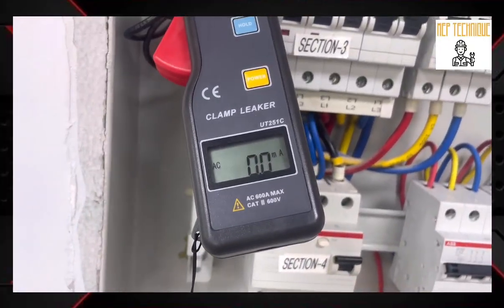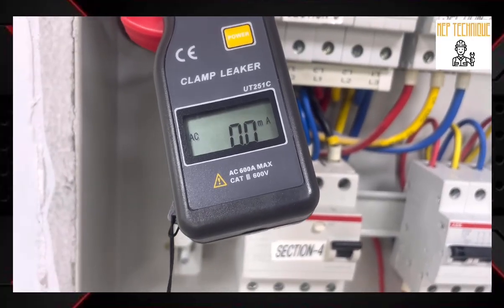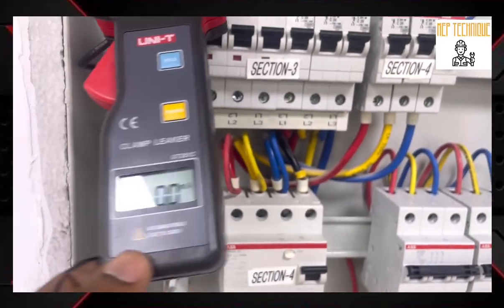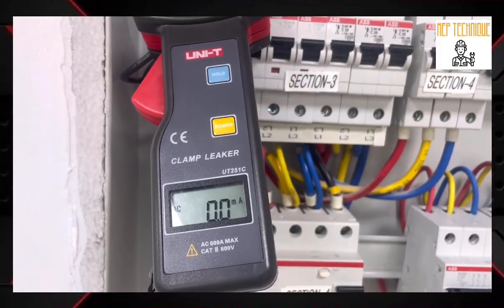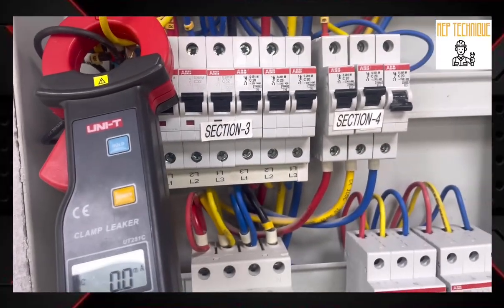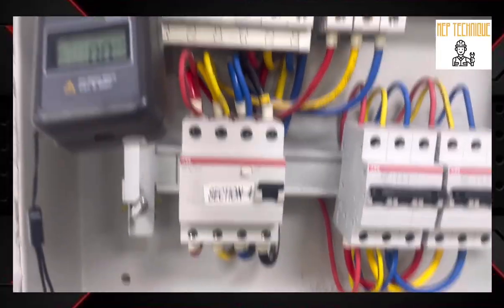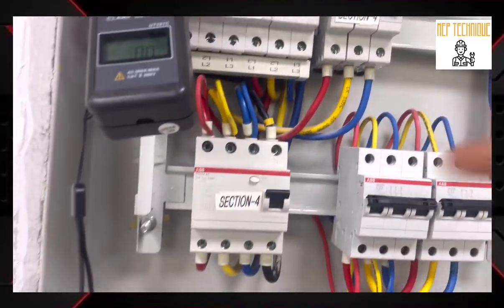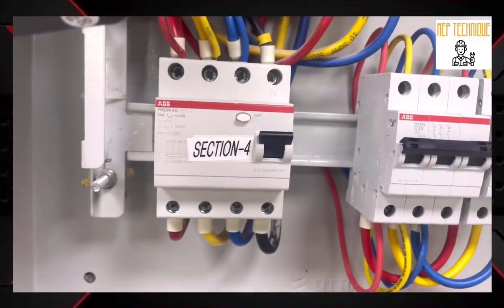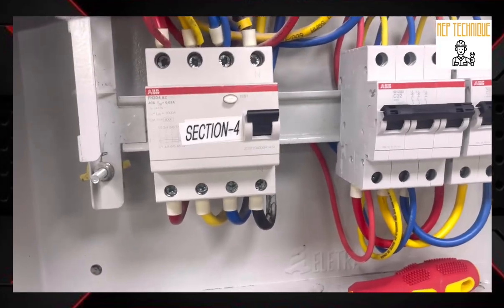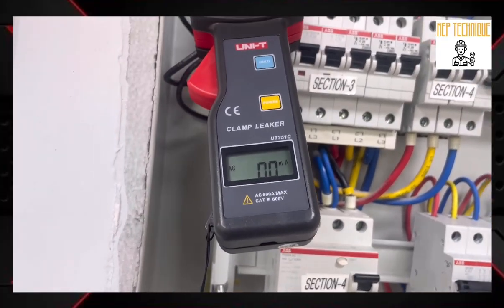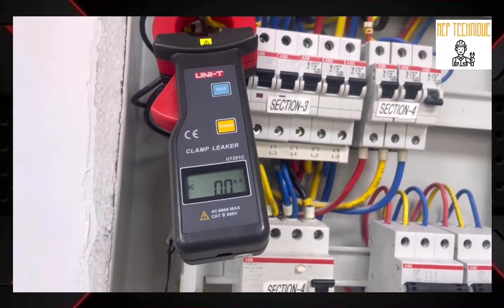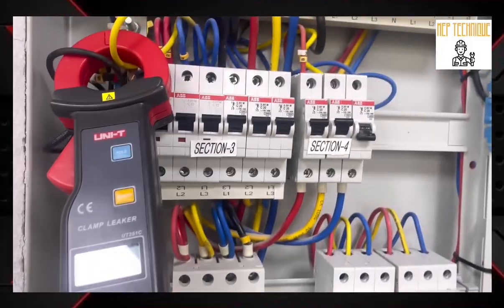Then you can see the leakage current. Here there is no leakage current shown in this meter. That means everything is right. If this leakage current exceeds 30 milliampere, exceeding the capacity, then your ELCB will get tripped. If it is tripping frequently, then there must be a leakage current. So with this clamp leaker, you will get to know exactly how much leakage current is in your electrical circuits.